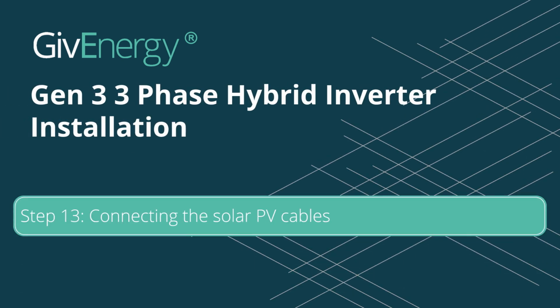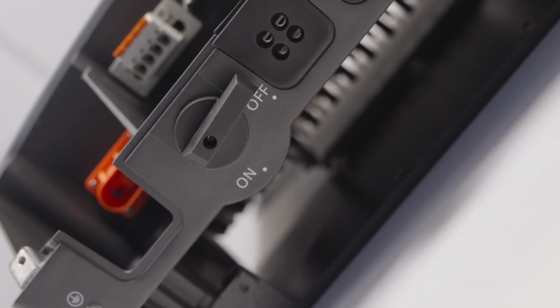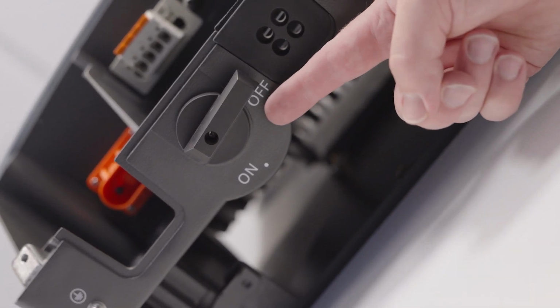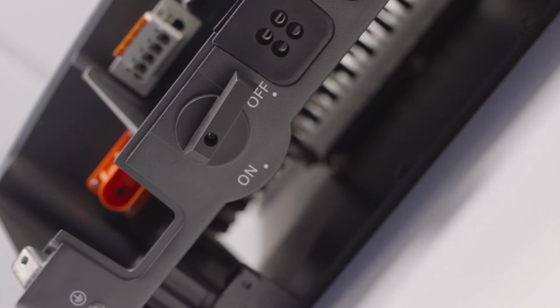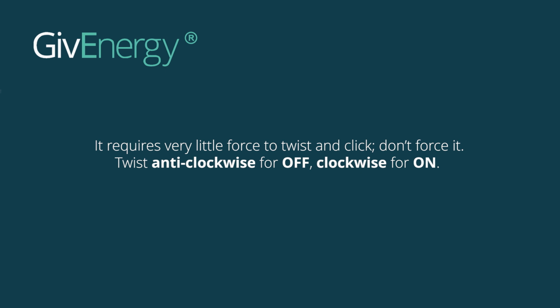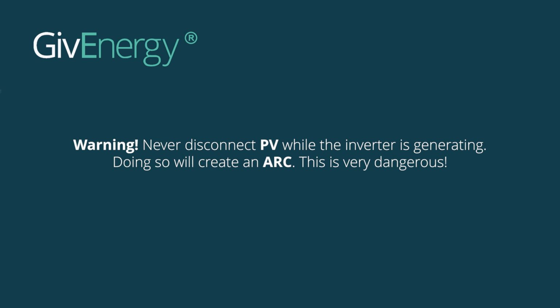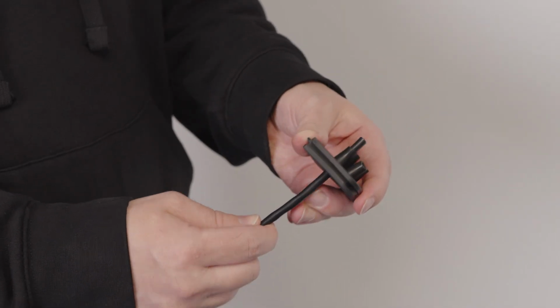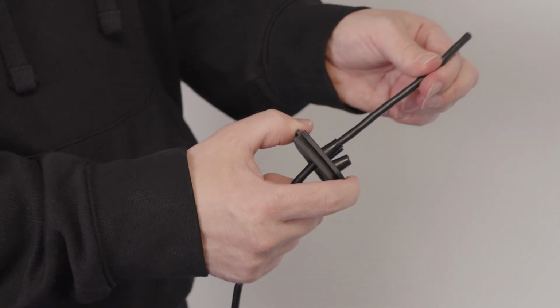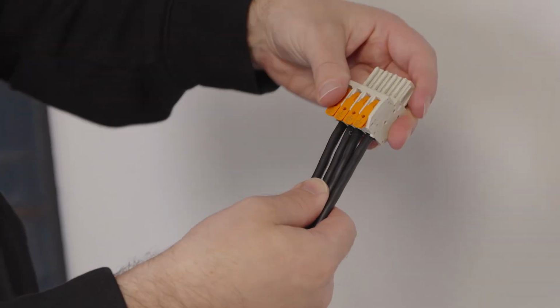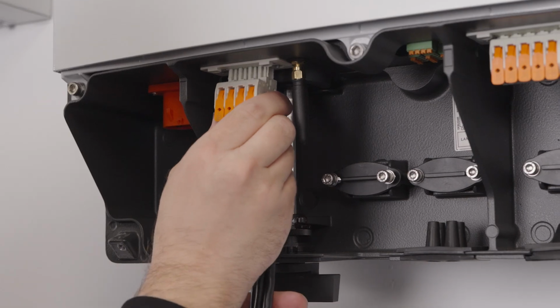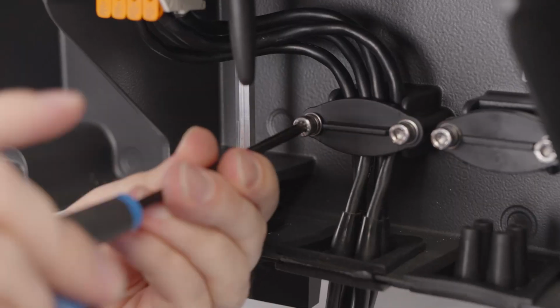Step 13. Connecting the solar PV cables. There is a rotary isolator at the bottom of the inverter here. This must be in the off position before making any connections. It requires very little force to twist and click. Don't force it. Twist it anti-clockwise for off and clockwise for on. Never disconnect PV while the inverter is generating. Doing so will create an arc, and this is very dangerous. Once the PV is isolated, pull the solar PV cables through the grommet. Ensure the polarity is correct. Ensure the Wago connector and each cable is securely in place by performing a tug test. Secure the cables into the saddle.